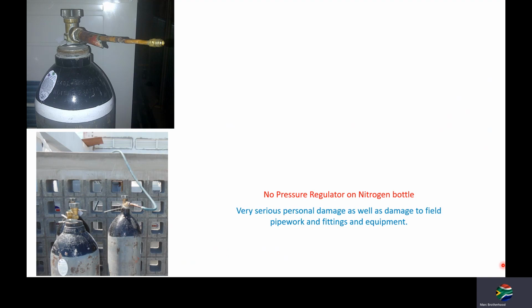Here we can see a nitrogen bottle standing at around 300 bar, pressurized without a pressure regulator. Here the installers have just put a normal oxyacetylene hose, purely regulating almost 300 bar just by throttling the isolation valve. So we can clearly see there's no pressure regulator on the nitrogen bottle. What's going to happen, you're going to have very serious personal damage, as well as damage to the field pipework, as well as your equipment.